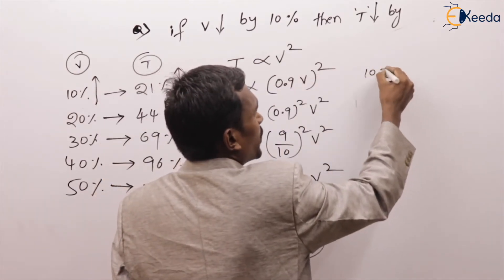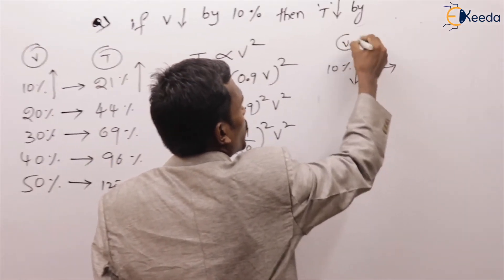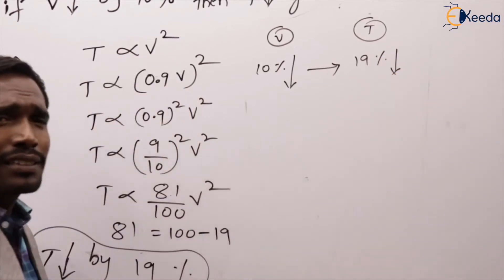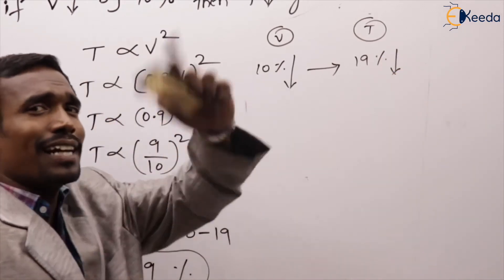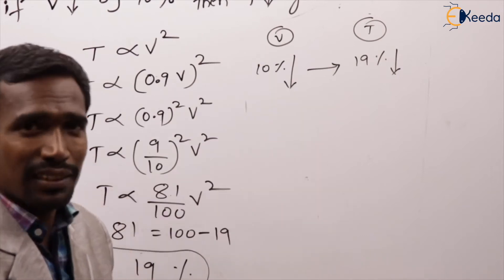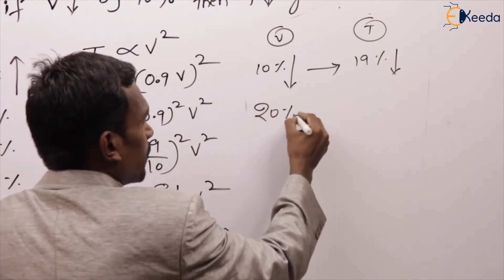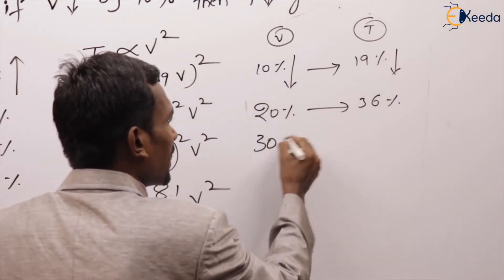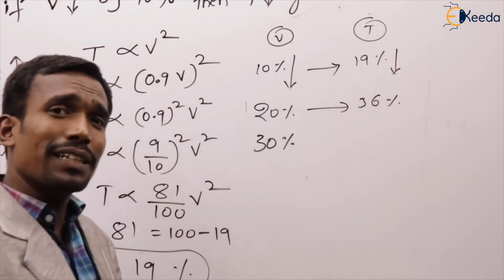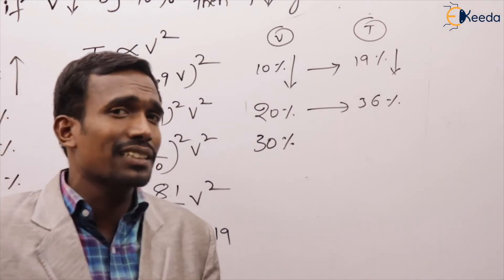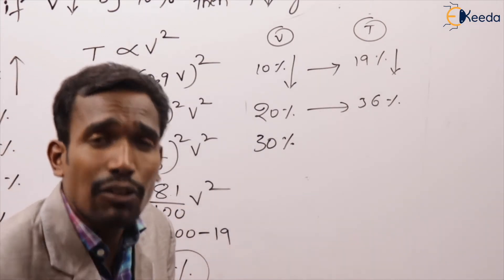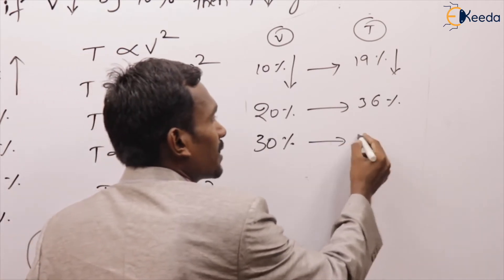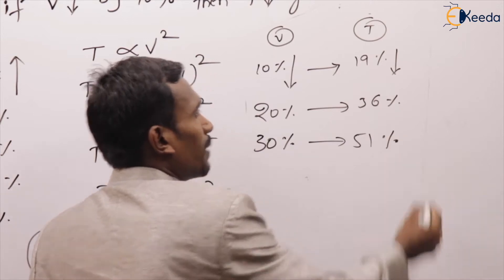If voltage reduced by 10%, torque reduced by 19% because 9 squared = 81. If voltage reduced by 20%, the answer is 36%. If voltage reduced by 30%, the factor is 0.7, so 7 squared = 49, which is 100 minus 51 — torque reduced by 51%.